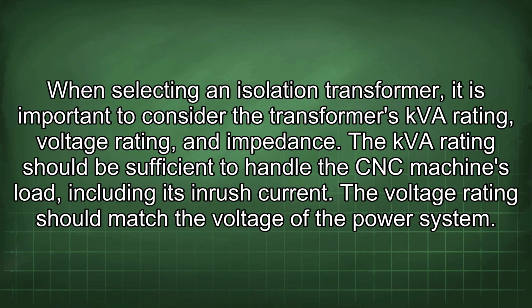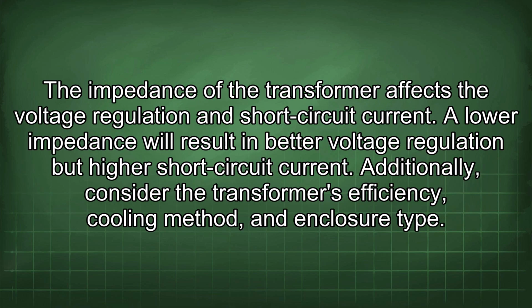When selecting an isolation transformer, it is important to consider the transformer's kVA rating, voltage rating, and impedance. The kVA rating should be sufficient to handle the CNC machine's load, including its inrush current. The voltage rating should match the voltage of the power system. The impedance of the transformer affects the voltage regulation and short-circuit current. A lower impedance will result in better voltage regulation but higher short-circuit current.